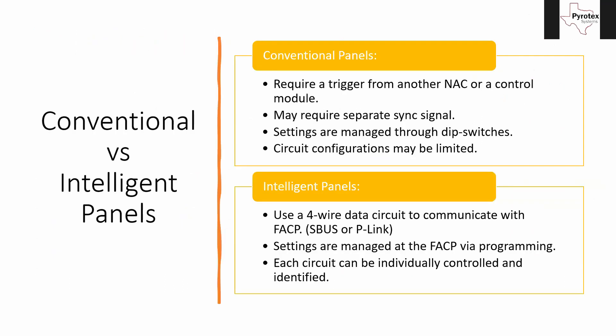The first thing to talk about: we have a couple different types of panels. One is conventional panels — these are the kind that have been around the longest. They require some kind of trigger to activate them. That trigger can come off of another NAC circuit within the building, from a control module, or a dedicated trigger circuit that comes off maybe the main control panel. That main trigger from the control panel can loop around and hit each NAC panel — the power supplies we're putting in.